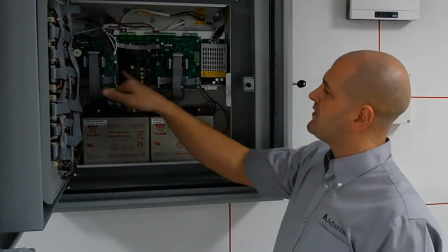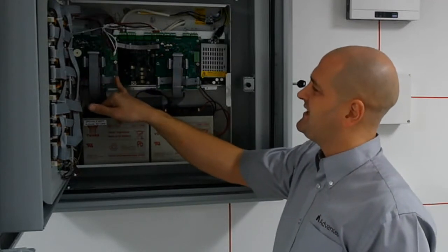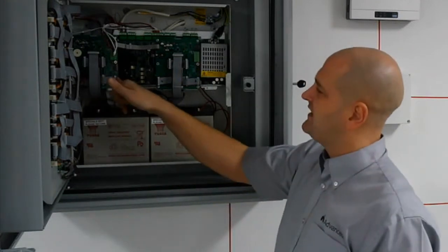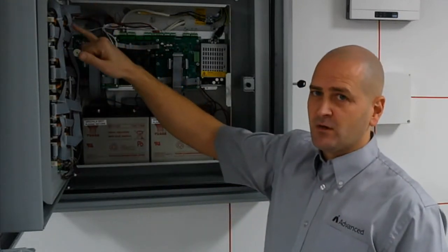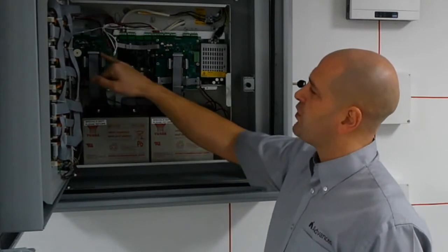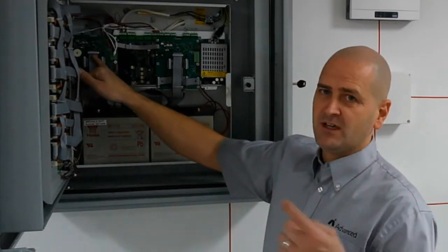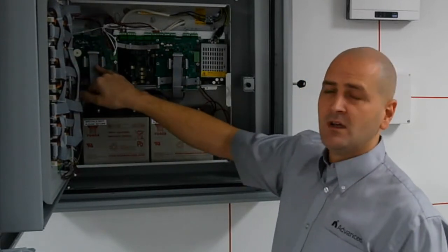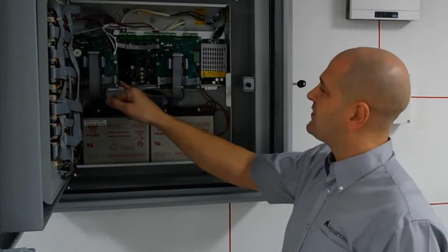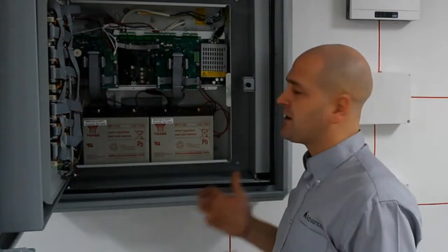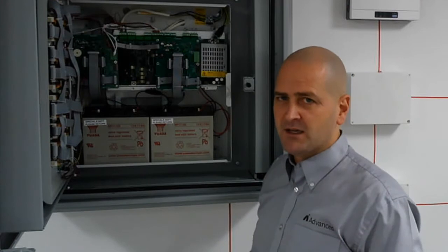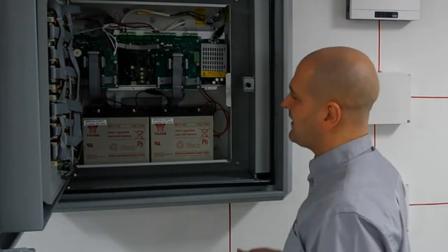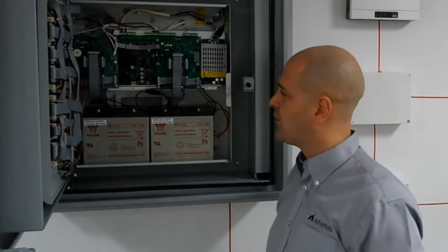So the 48-way IO cards, we have 16 inputs and 48 LED driver outputs. The 16 inputs are used for your fire and rescue service toggle switches, and then the appropriate LED indication, your activation, your alarm LED and your fault LED is driven from the same PCB. These components obviously need to be configured through our PCNet software package, so we need to install the software, which you can freely download from our website, and then we can use it to configure the equipment.